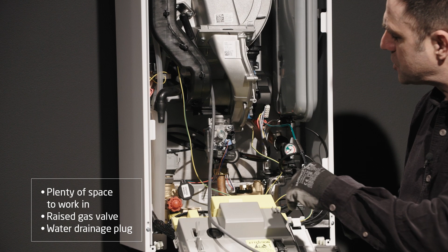So for example, if you're changing the plate-to-plate heat exchanger, no matter how much you drain the water out, you're always going to have a little bit of water left over in the back of the heat exchanger. And we've raised the gas valve up here, so there's no chance of that being damaged. We've also got a nice little plug in the bottom of the unit. You can see that there, a little groove. Any water that runs into the bottom of the unit, you can open the plug up and drain it into your bucket underneath.